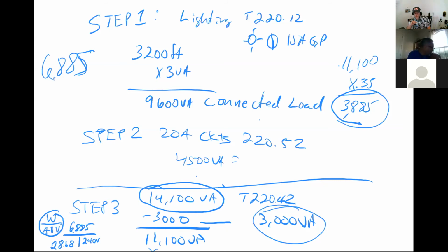What we just calculated — where did you get that derating, and where was the table? What part was it under? The table is 220.42. If you look on page 72 where that table is, down at the bottom left-hand side, you see the beginning of part 3. So everything that occurs after the bottom left-hand corner of page 72 is a feeder calculation.